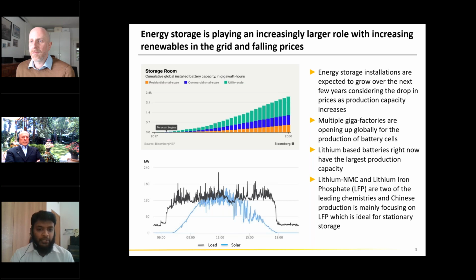What I have on the bottom left corner shows we're having the same problems on an off-grid system much earlier than what you're seeing on the grid system. The curve on the lower left is an actual off-grid site, around 200 kilowatts, that we are currently operating. You can see the solar, the blue line, is at the load curve, and the load curve itself is quite peaky because they have big baling machines, and on top of that we also have highly intermittent solar energy there.